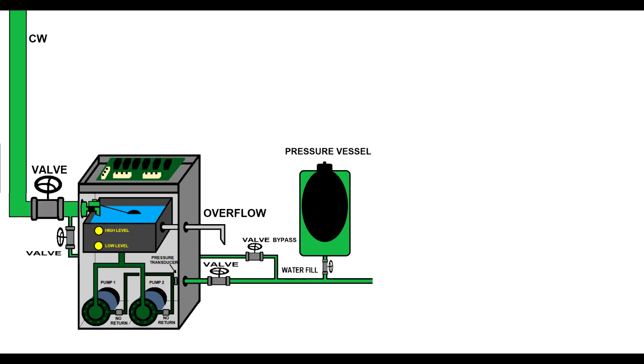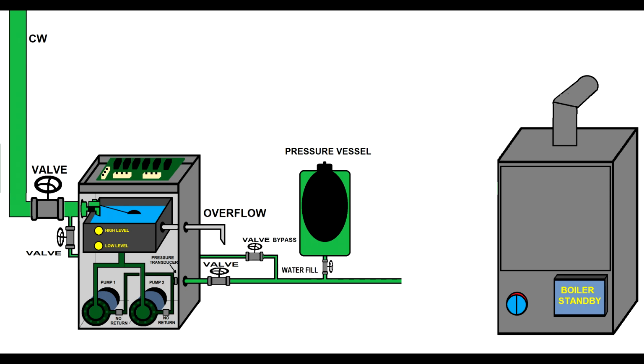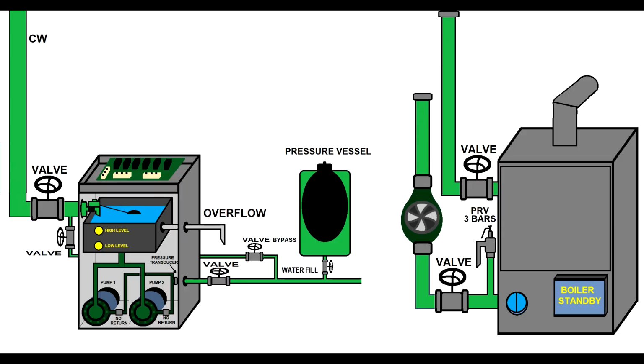Now let's build our heating system. Here's your pressurization unit. When you start installing a pressurization unit, before you connect it to the mains, you have to make sure that you attach a pressure vessel to the system, and I'll explain to you later on why the pressure vessel is so important. Obviously, because we're talking about a heating system, we have to fit a boiler into the system, which is the heart of the heating process. To transfer the heat, the boiler needs pipes and a pump to circulate the heating agent through the heating system. As you will see in this picture, the pressurization unit pipe is connected to the heating system main pipe.